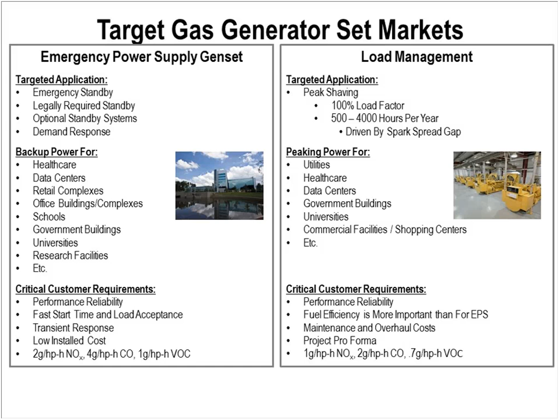You're going to be at the maximum level on any standby engine that you have. Now, depending on the system you buy, you may end up with a standby generator meeting the same classifications as in the diesel world, where you'd have 130-degree temperature rise over 40-degree for that generator. But the engine itself will always be rated as a continuous engine, whether it's in standby or in a load management application for a gas engine.